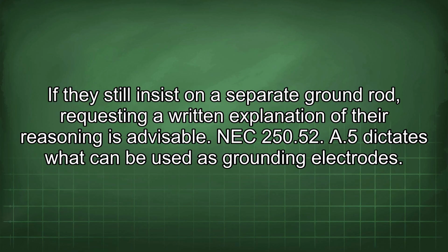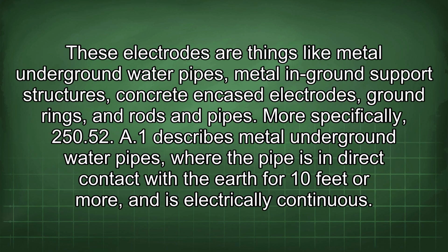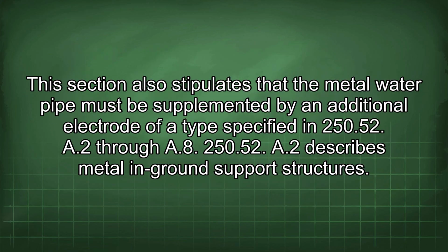NEC 250.52(A)(5) dictates what can be used as grounding electrodes. These electrodes are things like metal underground water pipes, metal in-ground support structures, concrete-encased electrodes, ground rings, and rods and pipes. More specifically, 250.52(A)(1) describes metal underground water pipes where the pipe is in direct contact with the earth for 10 feet or more, and is electrically continuous. This section also stipulates that the metal water pipe must be supplemented by an additional electrode of a type specified in 250.52(A)(2) through (A)(8).